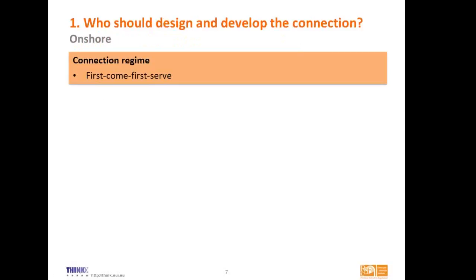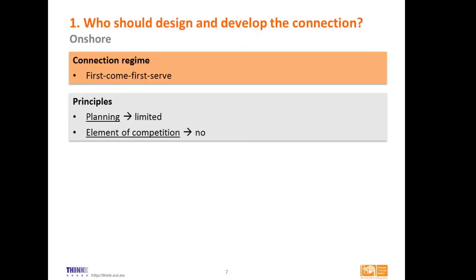First, onshore — how do we connect generators? The regime is referred to as first come, first serve. A generator developing a power plant goes to the TSO to ask for a connection, and the TSO deals with these requests on a first-come-first-served basis — a very simple procedure. If we look at this from two points of view — planning and competition, two important principles for transmission investment — planning is quite limited under this scheme, and there is no real element of competition since only TSOs are able to design and develop connections.